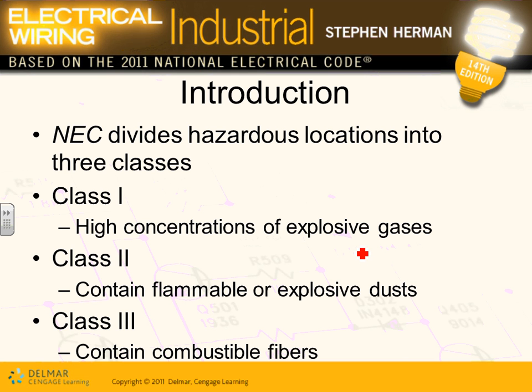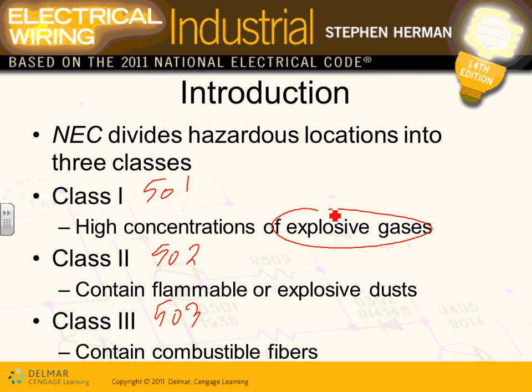So let's talk about the 3 locations that the code book classifies as hazardous locations, which means when you install a power system in these locations, you have to pay a lot of attention to the type of material, the type of installation and the type of wiring in order to meet the code. The first one is Class 1. Class 1 is 501, Class 2 is 502, and Class 3 is 503 in the code book. The areas classified as 501 have a concentration of flammable, explosive gases.